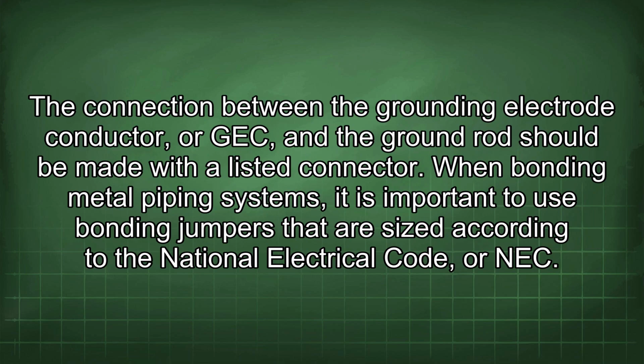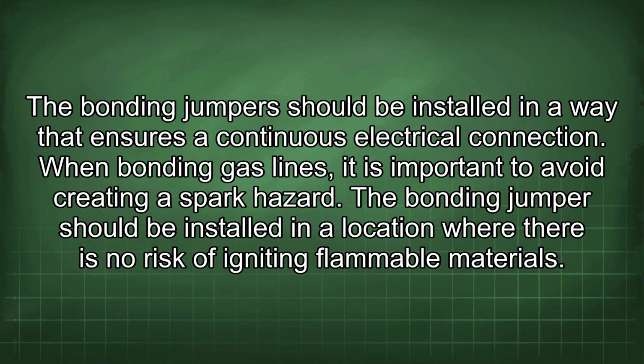The connection between the grounding electrode conductor, or GEC, and the ground rod should be made with a listed connector. When bonding metal piping systems, it is important to use bonding jumpers that are sized according to the National Electrical Code, or NEC. The bonding jumper should be installed in a way that ensures a continuous electrical connection. When bonding gas lines, it is important to avoid creating a spark hazard. The bonding jumper should be installed in a location where there is no risk of igniting flammable materials.